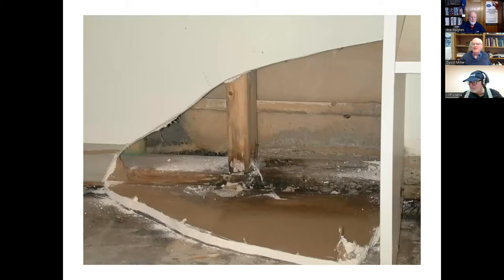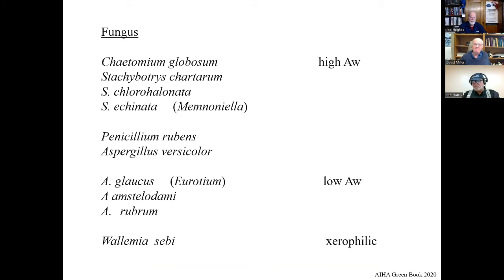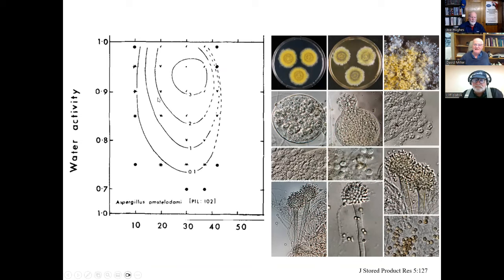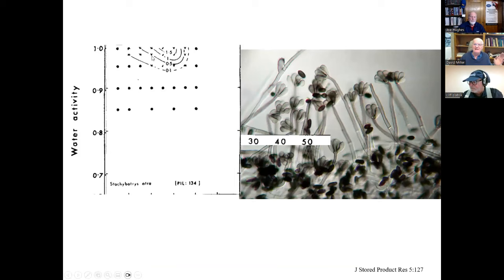So if you think about a building like the one that I showed you a couple of times that had a failure, that didn't necessarily happen anytime right after the flood. So it may not have been smells, there may not have been, you know, after it was dried, and at that time they weren't as aggressively worried about wall cavities as we would now, I think. So basically it happens fairly often that the fungus isn't happy, but it's not unhappy either, which is the point I can make about that. So if you think about moisture and you say, well, it's got to be pretty wet for Stachybotrys, well, that's true. It does need to be pretty wet for Stachybotrys, but it can grow, especially at cooler temperatures, under a little drier conditions too. It just takes longer. So it's not just the one property of water activity.